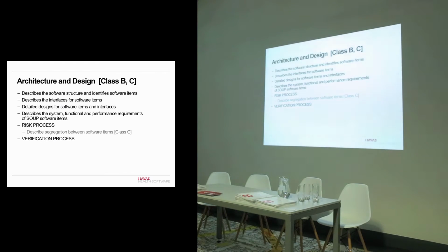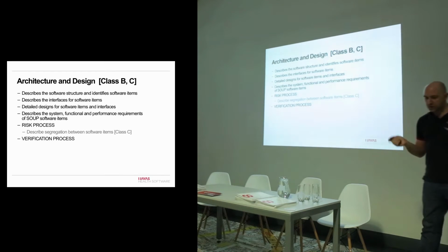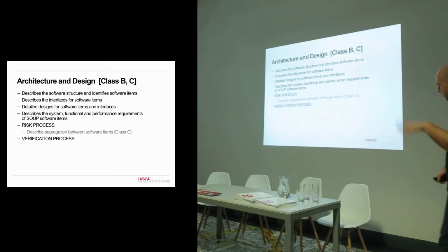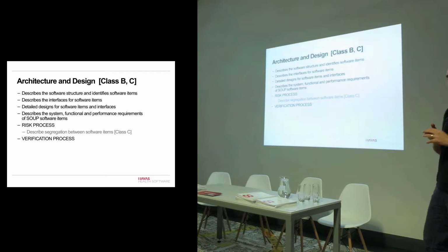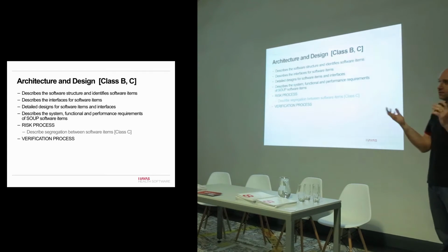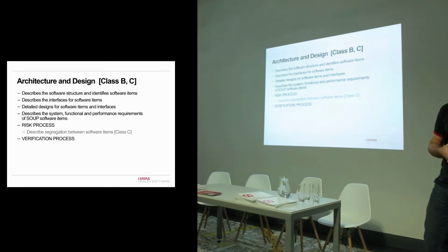The next thing is the architecture and design. Again, this kind of process will generate certain documentation. What it's really around is the higher level: how does this thing work? What are the major component parts, what hardware will it use, and how will that hardware interact? What parts of the software, what parts of your system will integrate with these things? For example, if it's a mobile application running on a phone, which phone, what version of that phone, what happens if that version changes, how is it interacting with the operating system? We treat the operating system as a SOUP thing. What other software is it going to interact with, and are you controlling those things? That's where SOUP all fits in.